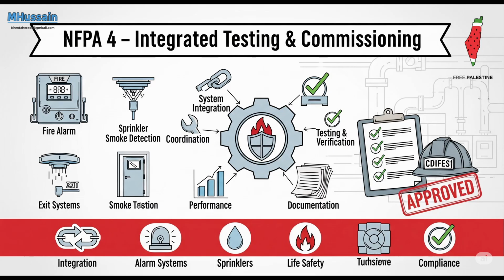That's the goal. So if we stick with that symphony analogy, what exactly is NFPA 4 trying to orchestrate? What's its core purpose? At its heart, NFPA 4 provides the definitive testing protocol. It's there to make sure that these integrated fire protection and life safety systems perform as intended. As intended, meaning working together. Precisely. It confirms the operation, interaction, and coordination of multiple individual systems. It's not enough for them just to be there. They have to collaborate flawlessly when things go wrong. So it's like the ultimate dress rehearsal for a building's emergency response systems. You could definitely say that. And the focus is squarely on that interconnection, right?